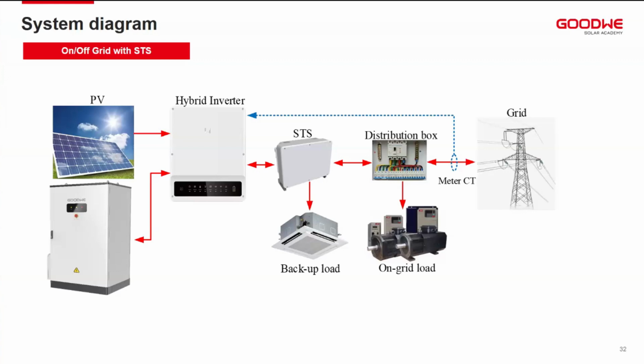So we have this scenario. The CTs are on the grid incoming line, just to monitor the grid incoming line for zero export or just to know the consumption and the load. Then we can connect on-grid loads to the on-grid port of the STS. Then the STS itself also has a backup port to connect the critical loads. Now the inverter side is a hybrid inverter, so we have strings or PV connecting to the inverter, and we have the battery, BAT, or even both series, BAT indoor or BAT outdoor, connecting to the inverter itself. So this is the typical scenario when you're connecting a single piece of inverter.